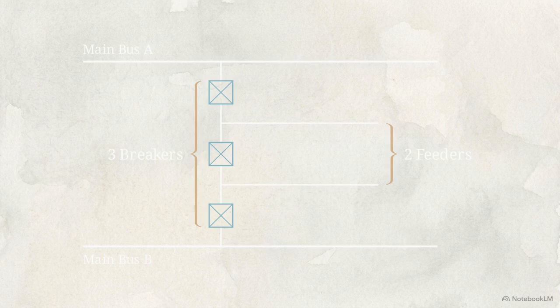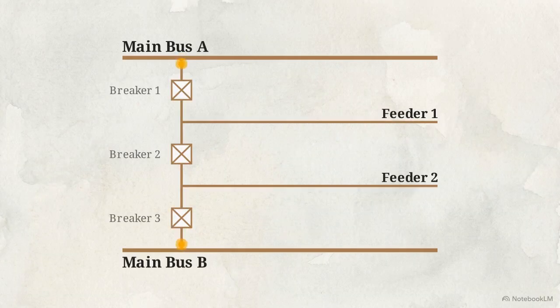This leads to Power Grid's definitive standard for 400 kV networks, the 1.5 breaker scheme. Exactly 3 circuit breakers are installed on a single crosstie to control 2 independent feeder circuits. This specific geometry yields a ratio of 1.5 breakers per feeder. It threads the needle between the low cost of a single bus and the high expense of a fully duplicated bus. In normal operation, both main buses are energized, continuously sharing the electrical load through the closed breaker array.